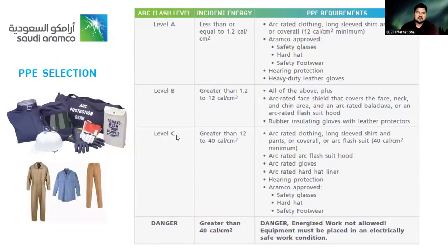And according to those levels, like arc flash levels, level A, level B, and C, or danger, we have to decide the PPE requirements. If we take an example of level A, less than or equal to 1.2 calories per square centimeter, the minimum PPE requirement is arc rated clothing, long sleeve shirt and pant or coverall, 12 calories per square centimeter minimum, and must be Aramco approved safety glasses, hard hat, footwear, hearing protection, and heavy duty leather gloves. These are the PPE requirements for level A.